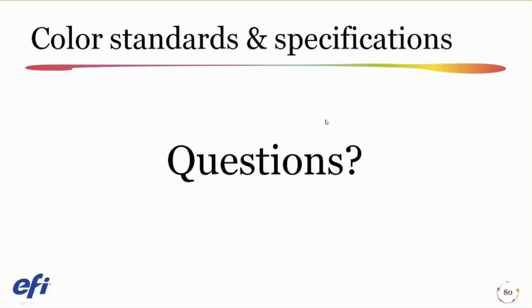Thank you, John. Second question is, how often should I calibrate my spectro? Spectrophotometers often do a calibration routine when you turn them on or use them for the first time. They often will either do an internal calibration, or in the case of the ES2000 device that we use at EFI, they'll tell you to put it on the plaque. By the way, the plaques are serial numbered to the device. Make sure you don't mix them up because they were calibrated to that plaque at the factory.